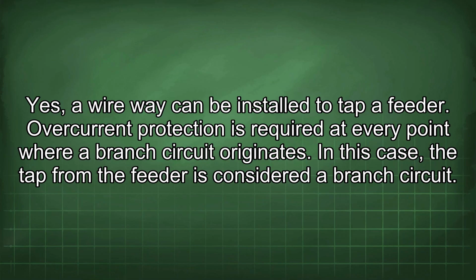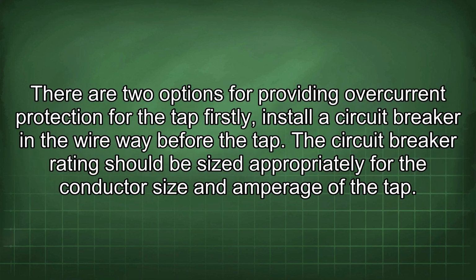Yes, a wireway can be installed to tap a feeder. Overcurrent protection is required at every point where a branch circuit originates. In this case, the tap from the feeder is considered a branch circuit. There are two options for providing overcurrent protection for the tap.